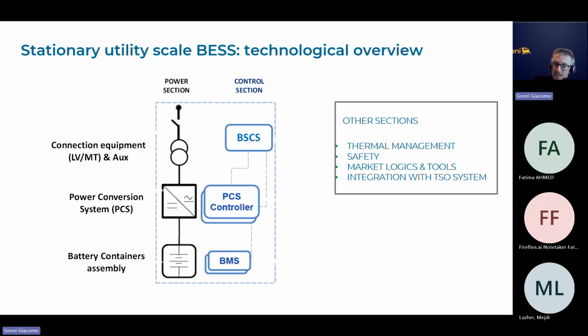One provider can give you the battery plus BMS. Another player can give you the inverter, the power conversion system that converts from DC, direct current, into AC, alternate current. Then you have all the connections and transformers from low voltage to medium voltage, the auxiliary systems. You need to cool the container and the cells to avoid thermal runaway and variations in round trip efficiency. The most complex part still remains at the battery cell level, but it is a little system - still, it is a container.